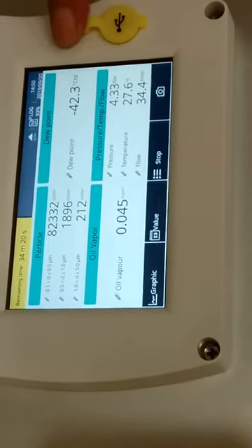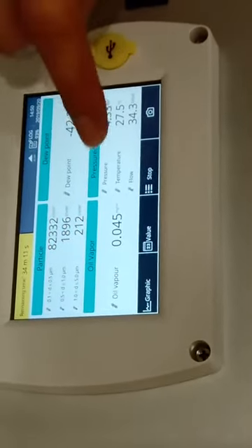If you see this red blinking, then these values are not within the class, they are above the class. We selected class one, so it's more than 20,000. At the second channel also more than 400, more than 10. So we have this up-direction alarm. But dew point is okay because I selected +2, which means -40, so lower. Oil +3 is also okay.